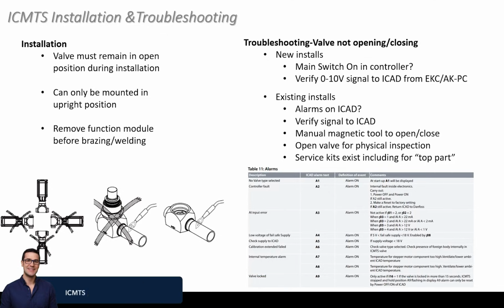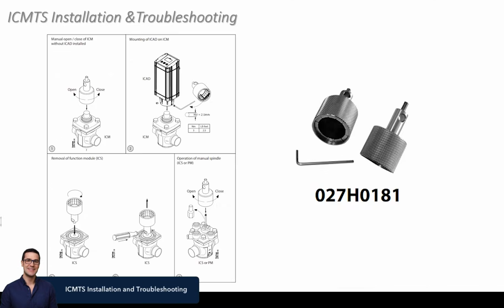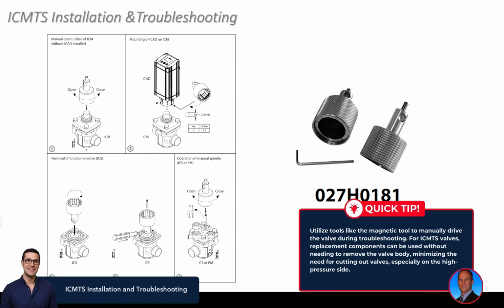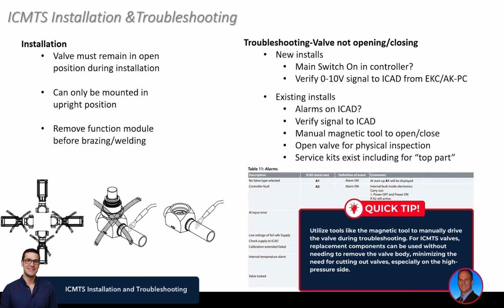Yep. And then if we've got an operational system, we talked about some things like the magnetic tool again that I've got here. So yeah, that can be used to manually drive the valve if we feel like that's something that we need to do as part of the troubleshooting. The valve can be disassembled, and then we have replacement components. Especially on the high pressure side where it's welding, anytime you're saying you got to cut a valve out, that's tough to hear. So luckily with the ICMTS, that's not the case most of the time. The valve body can stay in place and the other components changed out.